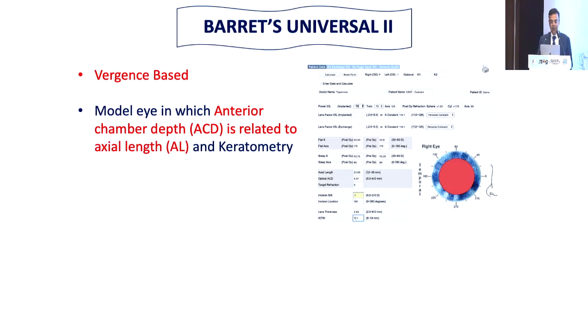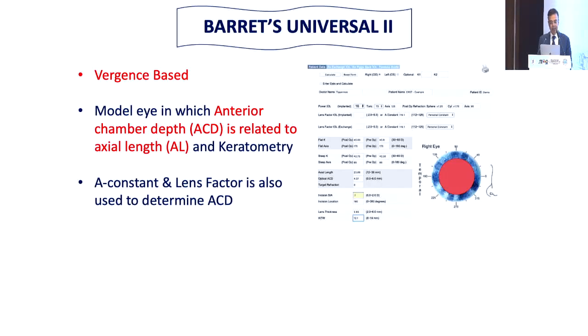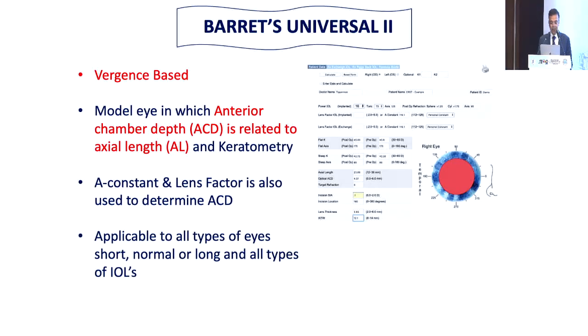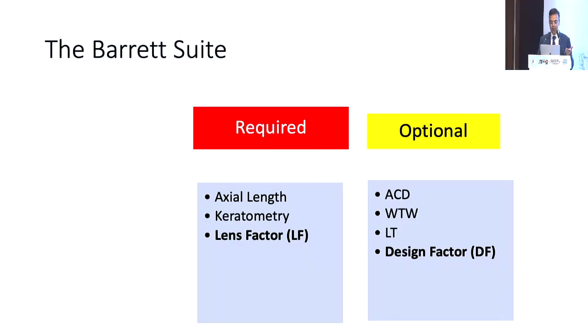So it's a vergence-based formula, the Barrett's Universal 2, and it's based on a model eye, and it will work with an A constant and lens factor, which is also used to determine the AC depth, and it is applicable to all types of eyes, as we just saw. And it can also be used for post-refractive surgery calculations when you use the Barrett's True K. So the Barrett's suite essentially requires you to have 3 compulsory things: the axial length, the keratometry, and the lens factor. And then optional ones are the anterior chamber depth, the white to white, lens thickness, and the design factor. So if you add these 4 variables, just like the Hill RBF, the Barrett suite becomes much, much more accurate.